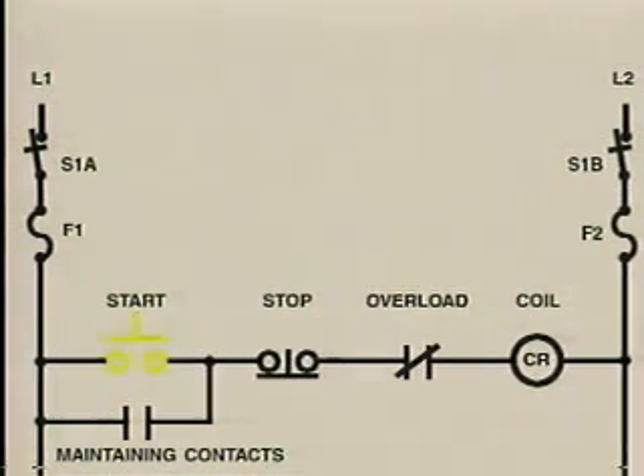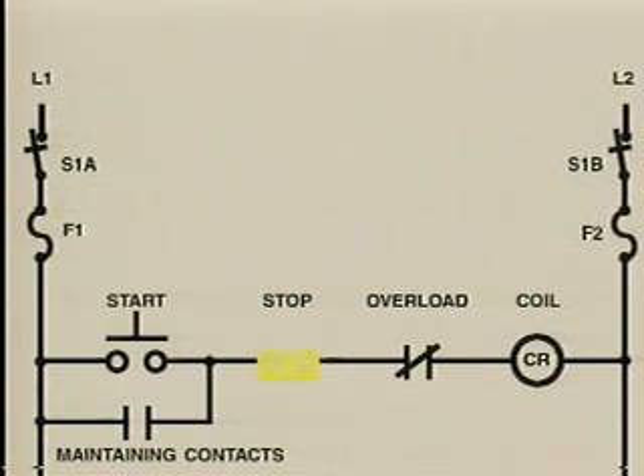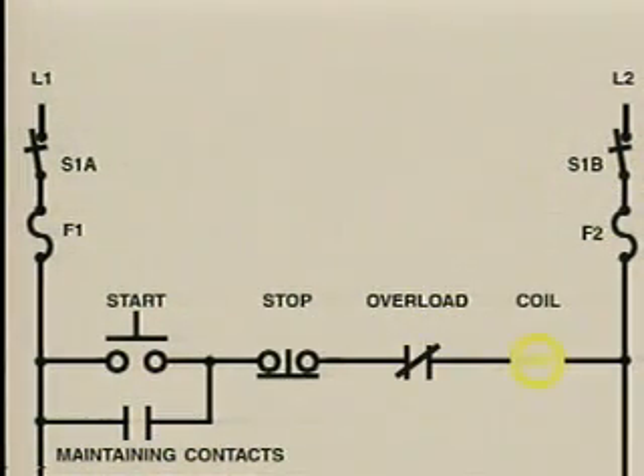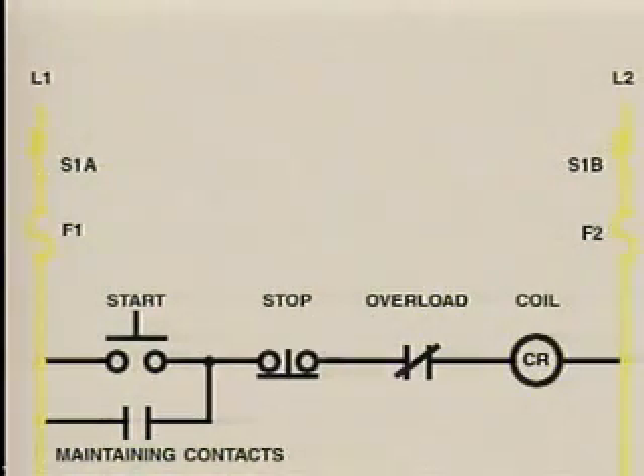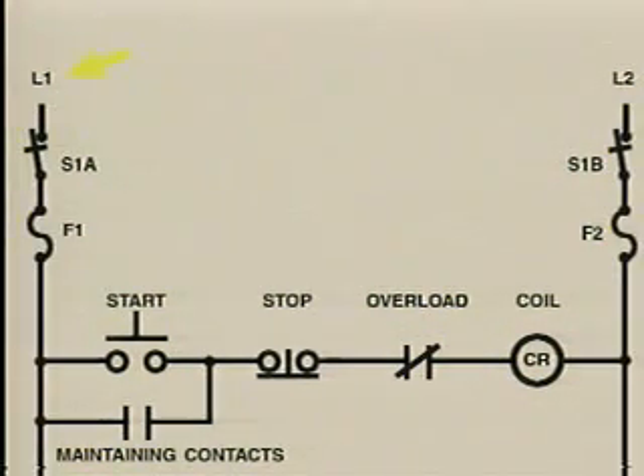This circuit consists of a normally open push-button start switch, a set of normally open maintaining contacts, a normally closed push-button stop switch, a set of normally closed overload contacts, and the control relay's coil. The circuit receives its operating voltage through these lines. One phase of the AC voltage, L1, is applied to the line on the left through one of the knife blades of the power switch and a fuse. Another phase, L2, is applied to the line on the right through another power switch knife blade and another fuse.